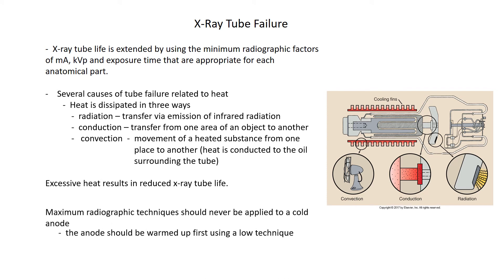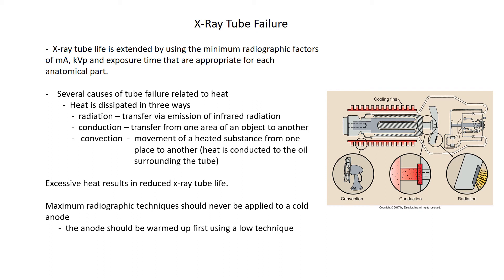Tubes do fail. X-ray tube life is extended by using minimum radiographic factors of mA, kVp, and exposure time appropriate for each anatomical part — lower techniques mean less heat. Several causes of tube failure are related to heat. Heat is dissipated in three ways: radiation, which is transfer via emission of infrared radiation; conduction, transfer from one area of an object to another; and convection, which is the movement of a heated substance from one place to another — for example, x-ray tube heat conducted to the oil surrounding the tube. Excessive heat reduces x-ray tube life, and maximum radiographic technique should never be applied to a cold anode; warm it up first using a low technique.